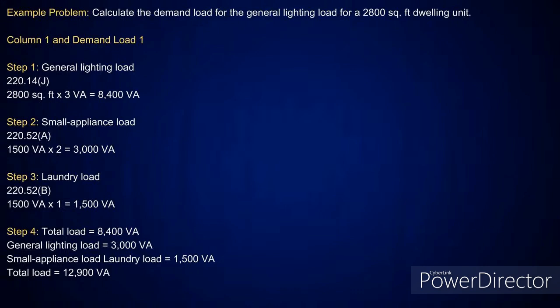Now, I've got a 2,800 square foot dwelling unit, and if you go over and you pick up 220.14J, you're going to pick that up, and let me say this, in the 2023, you're going to see that change also. That section has changed. So that's why we're going to have to do a new 2023 because of all the section changes. Now, in the 2020, it tells you to take that at 3 VA per square foot for a dwelling unit. So I take 2,800 square foot at 3 VA, gives me 8,400 VA.